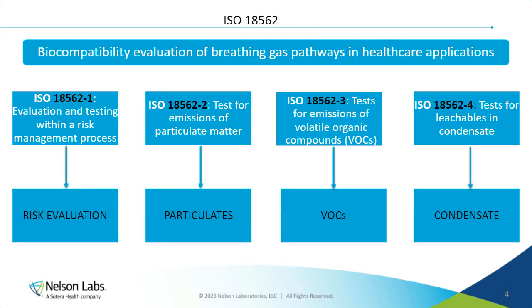As a further introduction to the 18562 series that will be applicable within this webinar, we have ISO 18562-1, the evaluation and testing within a risk management process; -2, testing for the emissions of particulate matter; -3, tests for the emissions of volatile organic compounds, which will often be referred to as VOCs. And then we have -4, testing for leachables in condensate. I really should have put an asterisk by this, or simply have just changed this to ISO 10993-18 for FDA submissions, but I'll touch on that shortly.